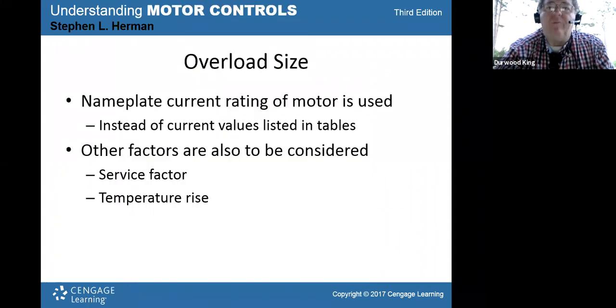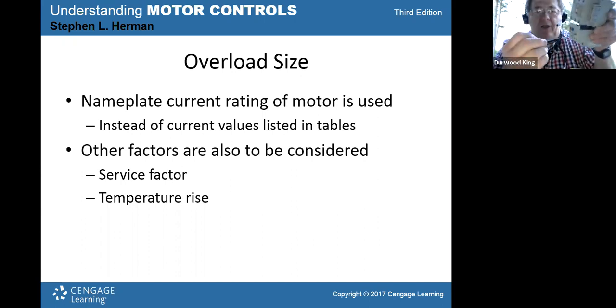Let me go forward. Here, your overload size. The overload size is actually based on the nameplate current rating of the motor used instead of the table values. The reason is that, whatever specific motor you're running at the time, whatever brand it is, you can physically go up to this overload and take that screwdriver and fine tune it right on the fly for whatever motor you have. So you dial that in, you take the nameplate amps.